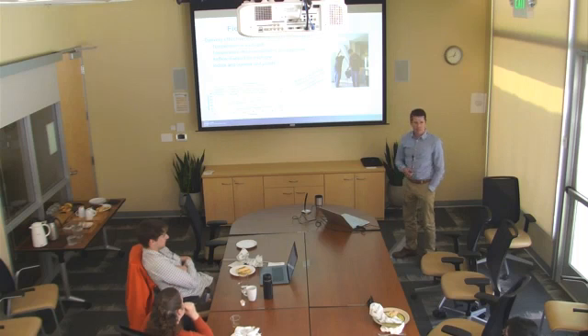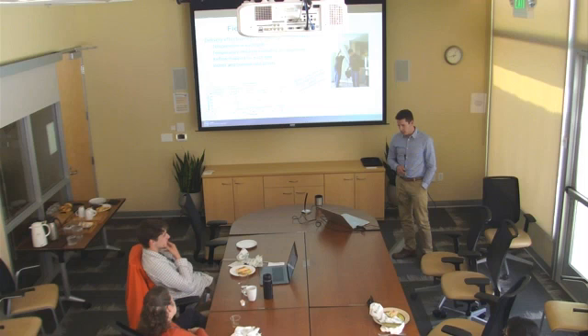Okay, so we took this whole lab test and its results and took it out into the field. We recommended they put in zoning equipment so we could look at the impact of zoning on delivery effectiveness. Again, we're really interested in that particular component because the equipment performance is fairly well known and easy to measure. So we had to measure the temperature at every grill. We had to measure the temperature and humidity at the equipment so you can separate the capacity going into the building through the grills versus the capacity produced in the equipment.